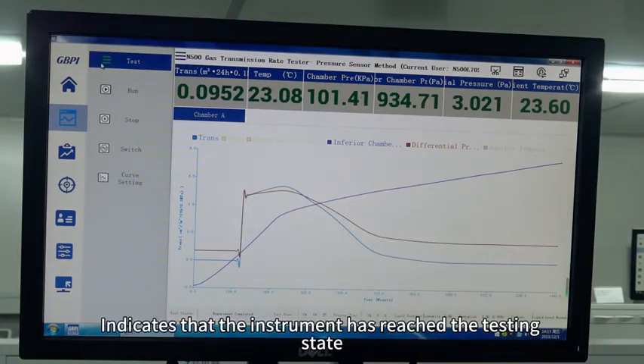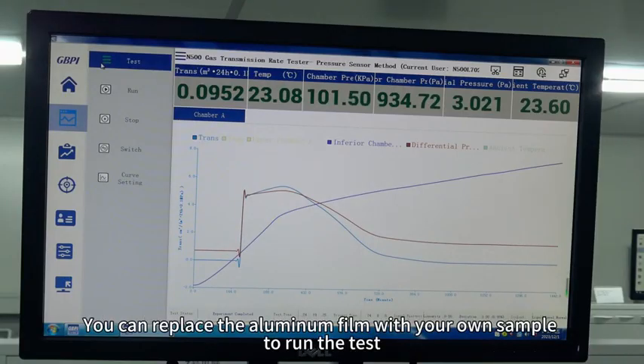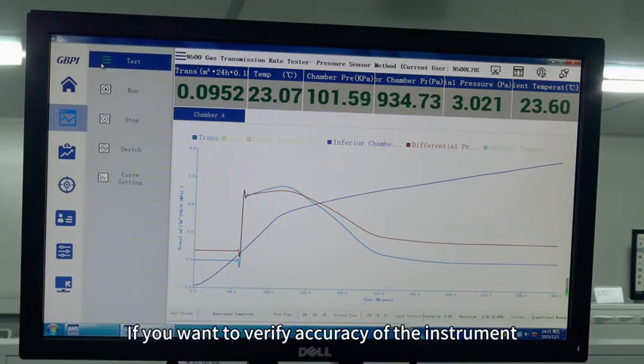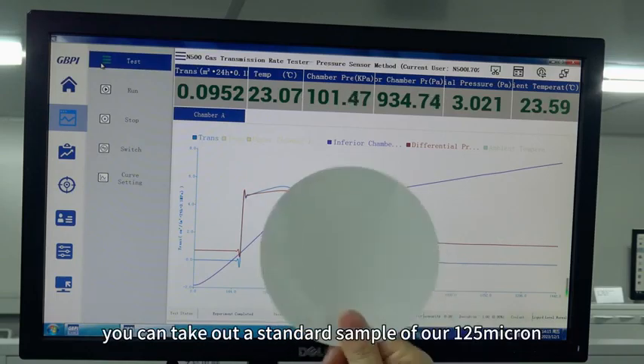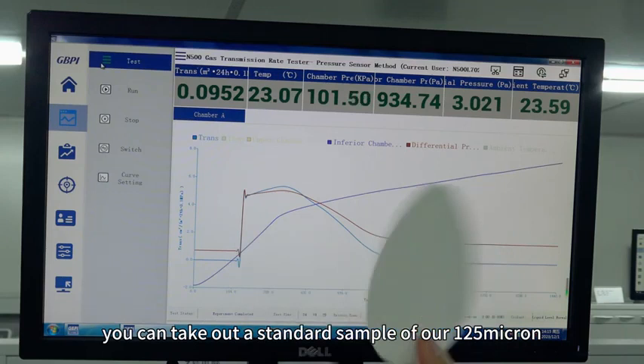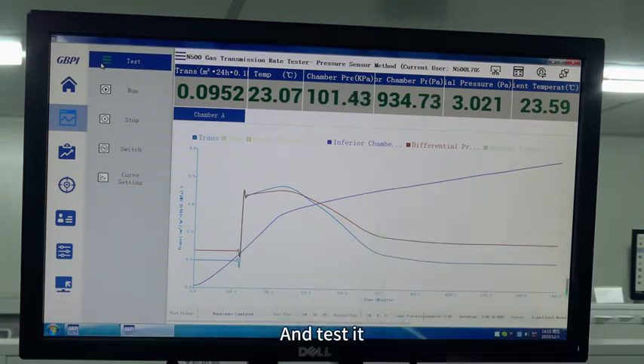This indicates that the instrument has reached the testing state. You can replace the aluminum film with your own sample to run the test. If you want to verify the accuracy of the instrument, you can take out a standard sample of 125 micron and test it.